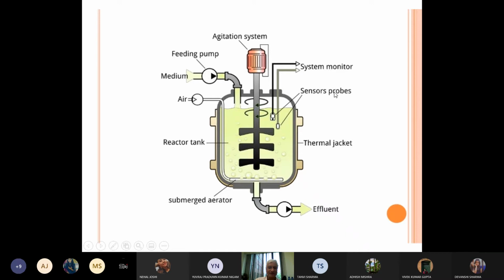Most of these things are controlled using a control panel. As I told you, in our time, even today, on my hand, 1000-liter fermenter, which was of Marubishi, I used to use, we used to get a burn. Because क्या होता था? You can imagine a 1000-liter at 121 degrees centigrade and 15-pound pressure. These are all ports which can easily break, or reverse, it can kill you. This hot media can kill you. And there are examples of mortality in accidents in fermentation.